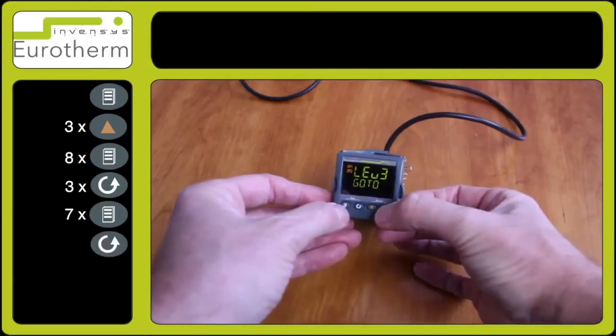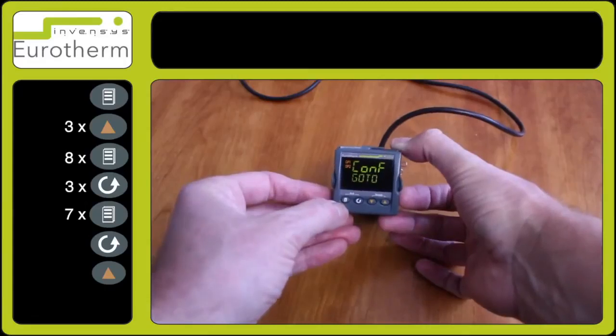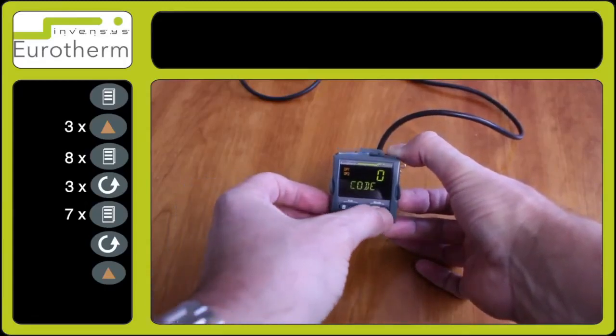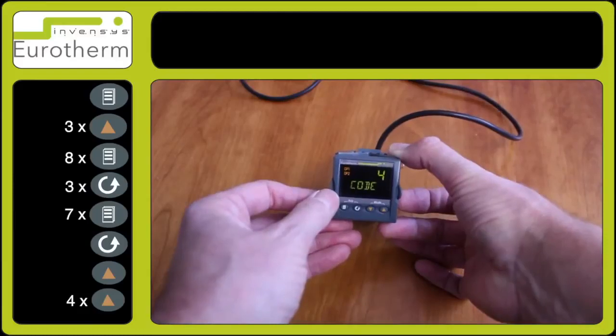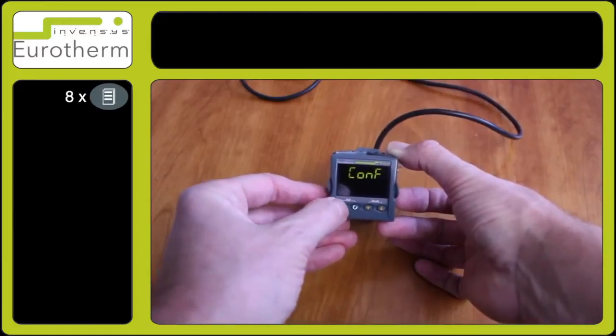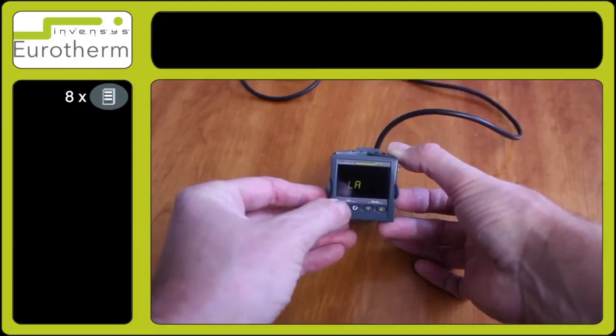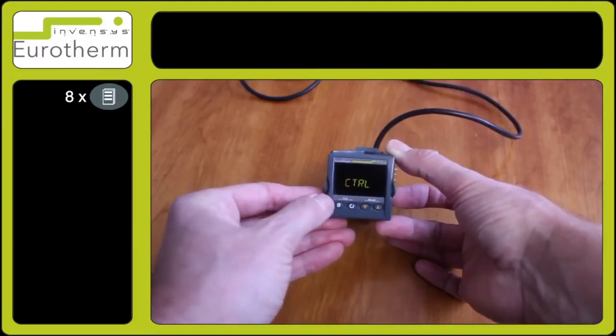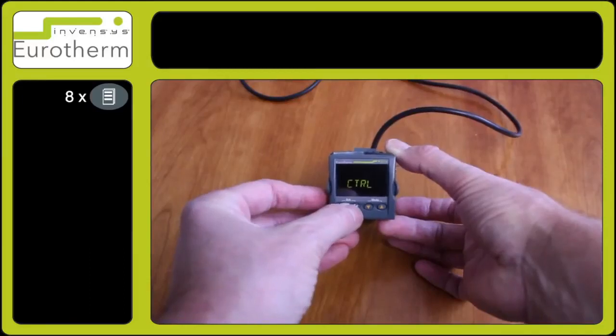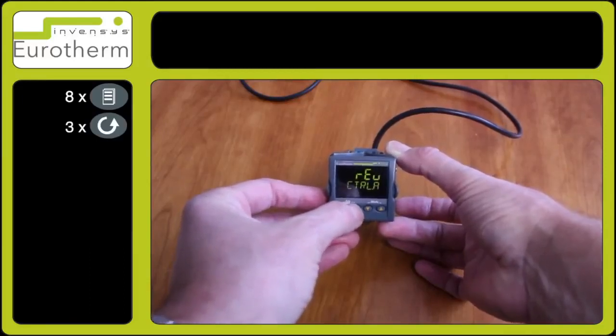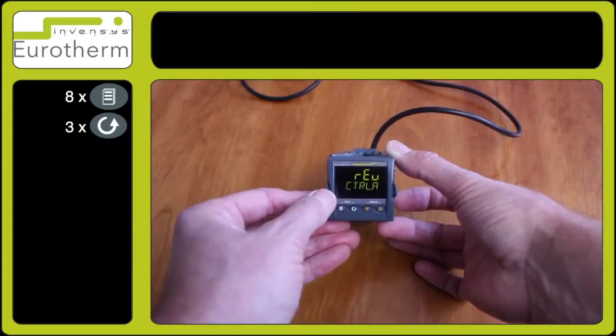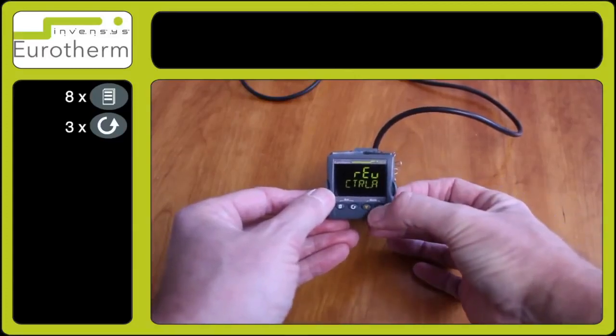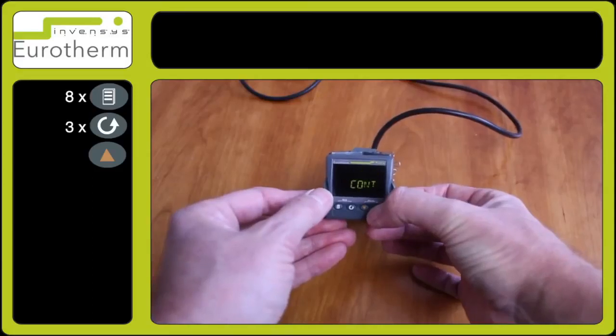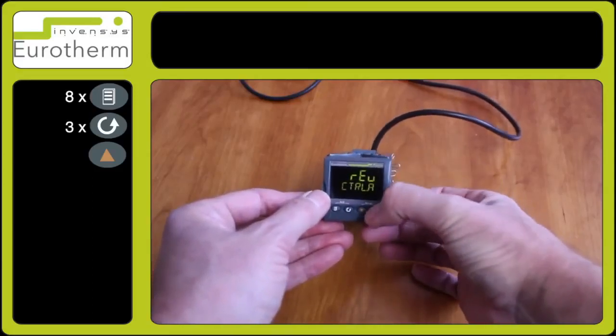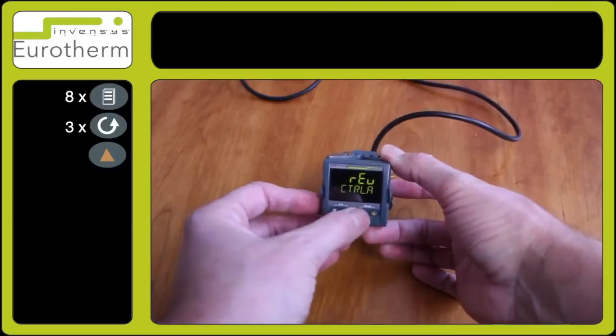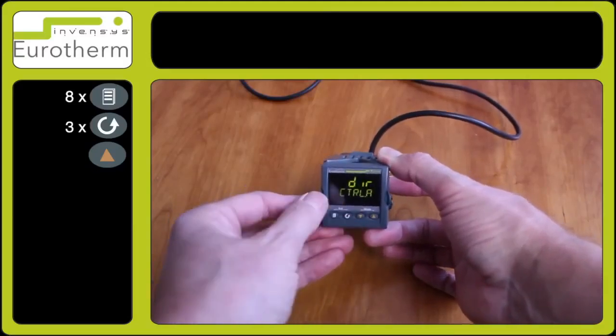press the scroll key, press the up arrow key for configuration, and enter number 4. Press the page key until you reach CTRL, the control list. Press the scroll key a few times for CTRL.A, and you can change this here for direct or reverse acting. This time I will change it to direct acting.